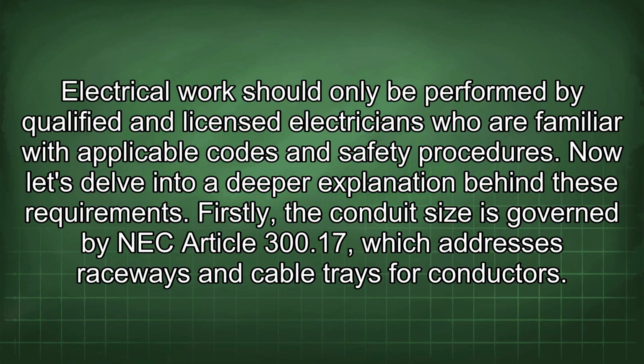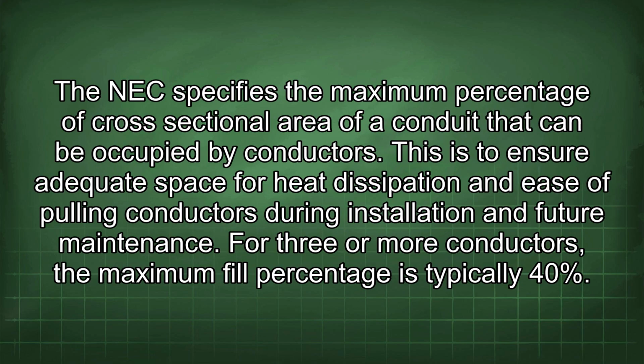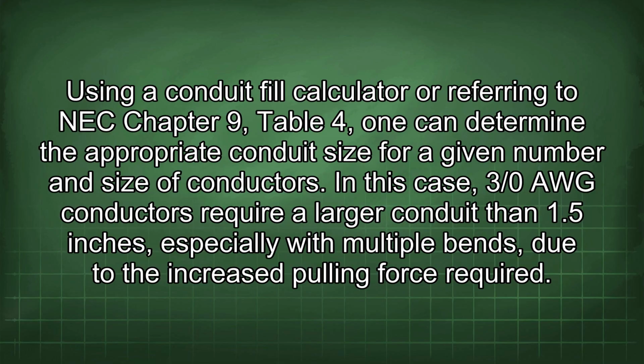Now let's delve into a deeper explanation behind these requirements. Firstly, the conduit size is governed by NEC Article 300.17, which addresses raceways and cable trays for conductors. The NEC specifies the maximum percentage of cross-sectional area of a conduit that can be occupied by conductors. This is to ensure adequate space for heat dissipation and ease of pulling conductors during installation and future maintenance. For 3 or more conductors, the maximum fill percentage is typically 40%. Using a conduit fill calculator or referring to NEC Chapter 9, Table 4, one can determine the appropriate conduit size for a given number and size of conductors.